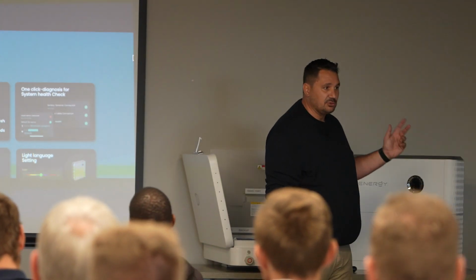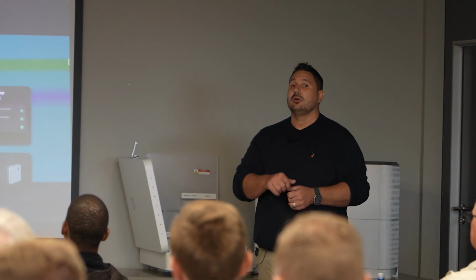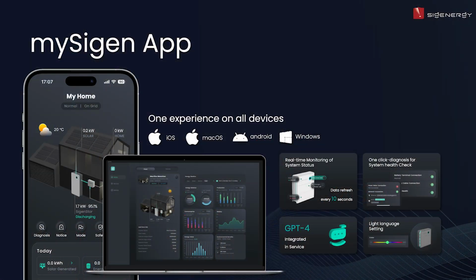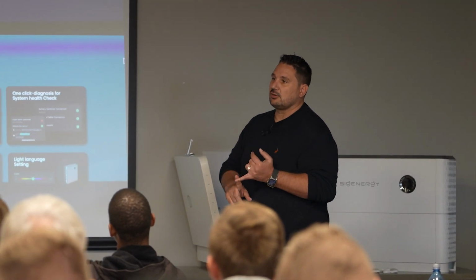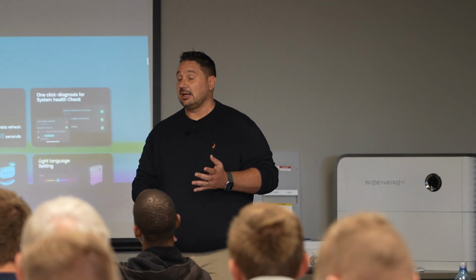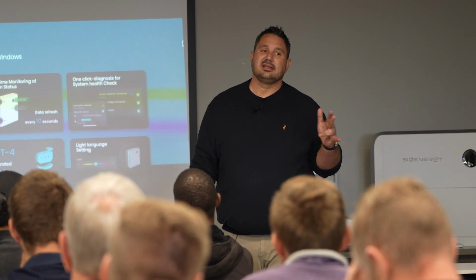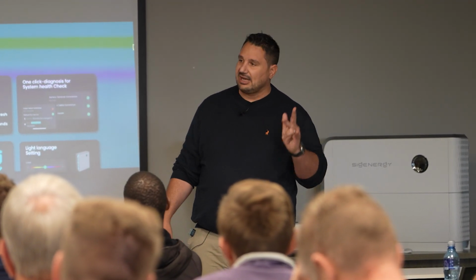They've got nice functionality like, oh, let's change the light from green to blue. They've got, I can input my electricity tariffs, or I want to have 60 or 70 or 50% battery backup. Those are the functions that's available for him to change. Or I want to be in self-consumption mode, or I want to be in Sigen AI mode, or I want to be fully feed into grid. That is what they can choose. They cannot set grid code settings. They cannot set anything else. And you cannot set the charge current for the batteries.